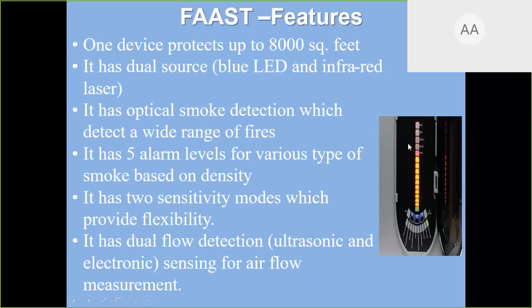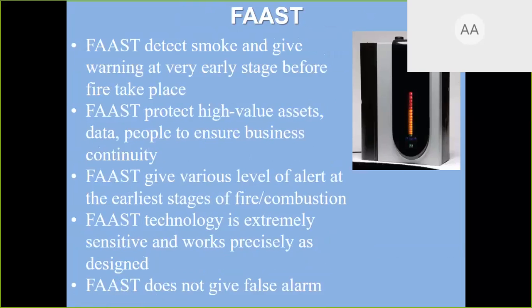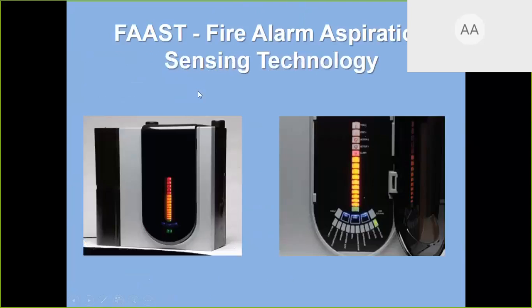So these are the features of FAST. And I told you that it will not give any false alarm. It is very, very sensitive and it will give you an alarm before combustion takes place, at a very early stage before the fire. So this is one technology which a company can opt for to avoid any fire incident. If something happens, it will give you an alarm and we can take quick action to prevent the fire. FAST, Fire Alarm Aspiration Sensing Technology.